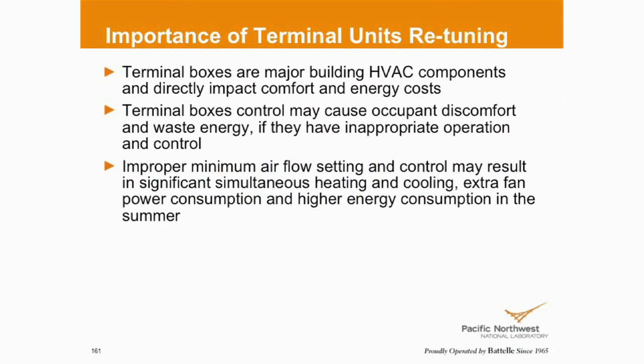Terminal boxes are one of the major building HVAC components for new buildings with VAV systems. So they have a big impact on comfort and energy use. If the terminal box minimum airflow set point is too high, that can cause some problems. You have to have a lot of reheat for the terminal box to compensate for the problem.